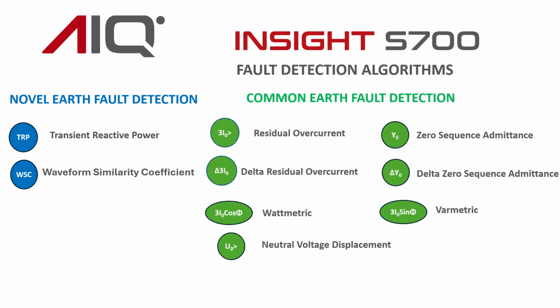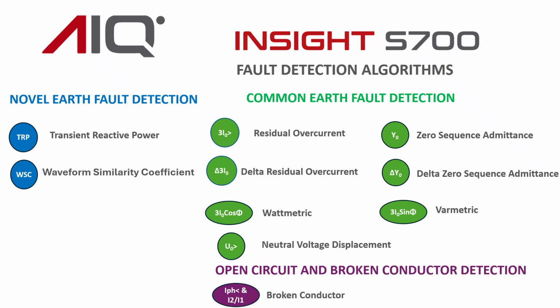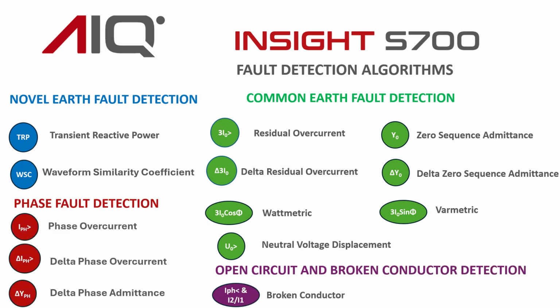There are a range of traditional earth fault detection algorithms together with broken conductor detection and phase fault detection. They are based on the fundamental frequency, magnitude and phase calculations and are selectable based on different neutral treatments and the S700's mode of operation, as explained in the following slides.